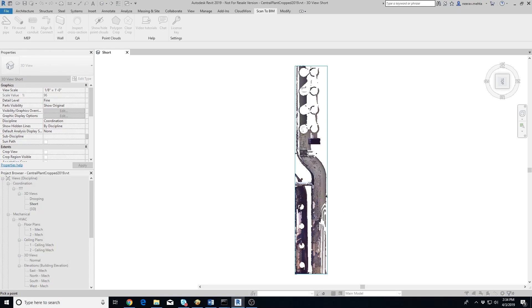Next click on a point on a duct that you want to extract. Make sure to click on the straight portion of the duct, away from elbows, tees, or any other object.